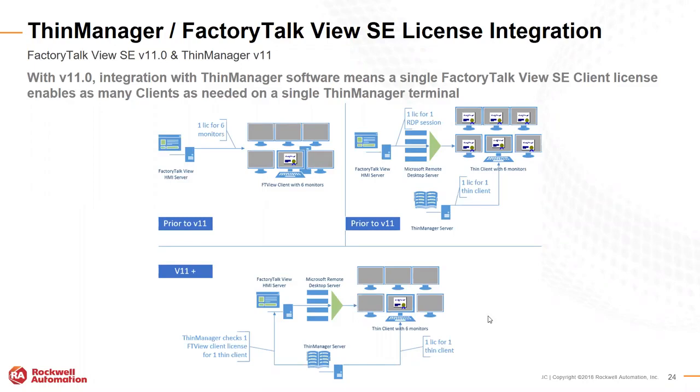So it depends on what you're trying to do. FactoryTalk View SE is pixel-based, so you do define what the resolution is, what your X and Y axis are. You have two options. You can either launch it with what's called FactoryTalk Viewpoint, an HTML5 conversion of the existing screens. The other option is to push it into Thin Client, because once it's displayed on the Thin Client side through Thin Manager, at that point you can then start doing this.